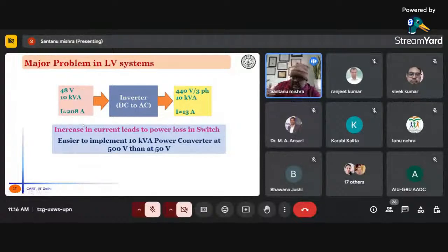So at our home level, if you are putting a rooftop panel, it will have a voltage of, let's say, 48 volt, with a rating of about 1 or 2 kilowatt, not 20 or 50 kilowatt. The reason is that input current makes a difference. I'll come back to the MNRE guidelines for grid connected inverters that people are buying, where they mention it should be somewhere between 2 to 3.3 kilowatt. They haven't specified a voltage exactly, but 3 kilowatt is what they're looking for. Even if you make a 3.3 kilowatt inverter with 48 volt, it's fine, because at the end of the day you need an inverter that can be put on a rooftop.